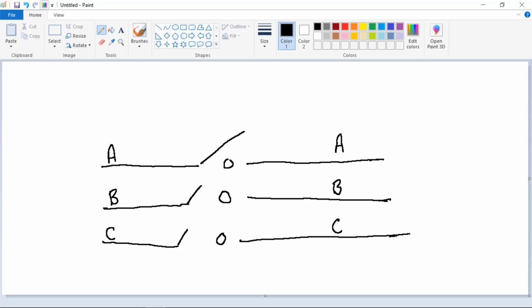So this is a diagram of the 2 feeders I had before, breaker A on the left and breaker C on the right. This is going to happen almost all the time, unless you've got a poor company out there on the switch install. So every time I install a new ground operated air brake switch or a new set of disconnect switches to create an open point on a feeder or a closed point if I need it later on, something's got to happen to make sure that everybody that uses it afterwards is going to be okay as far as phasing is concerned. Now, back to the diagram here.